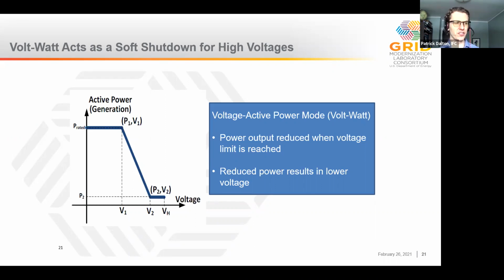What this function does is, for normal conditions, the DER just produces the power it has available. So if it's a solar unit, it's going to produce as much power as it can from the sun. But if for some reason the voltage got to this very high level, it's going to start to gradually back off that production in sort of a soft shutdown type of approach.